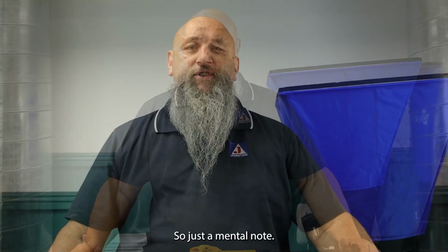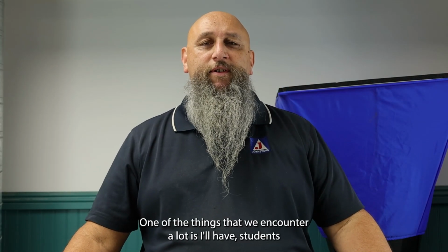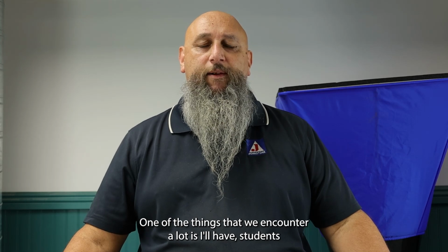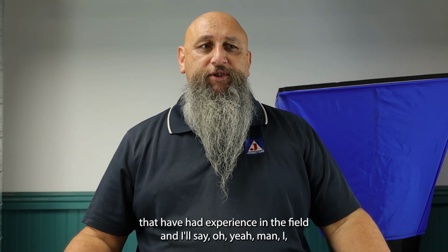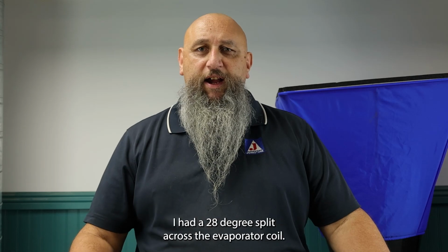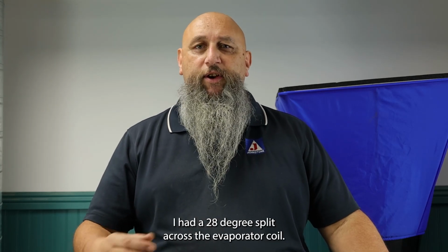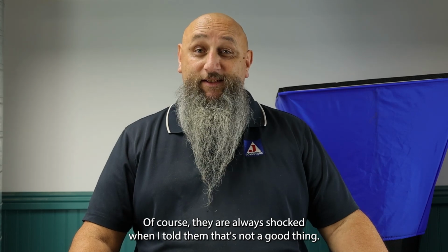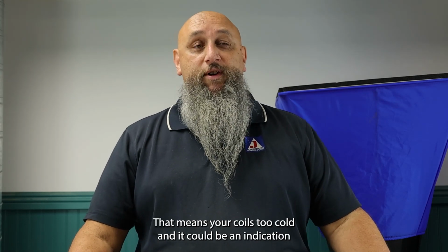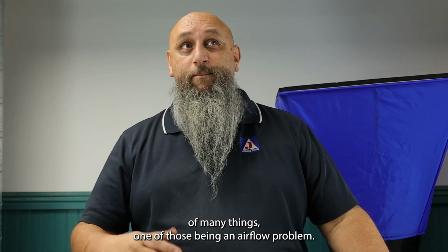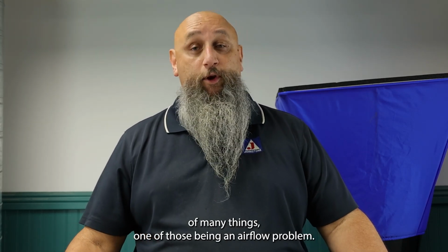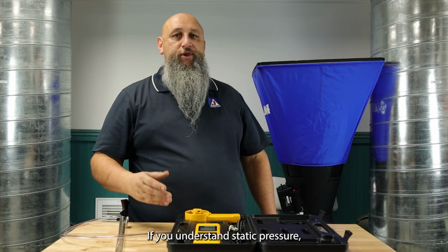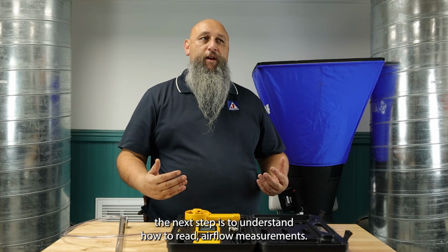So just a mental note, one of the things that we encounter a lot is I'll have students that have had experience in the field, and they'll say, oh yeah, man, I had a 28-degree split across the evaporator coil. And of course they're always shocked when I tell them that's not a good thing. That means your coil's too cold. And it can be an indication of many things, one of those being an airflow problem. If you understand static pressure, the next step is to understand how to read airflow measurements.